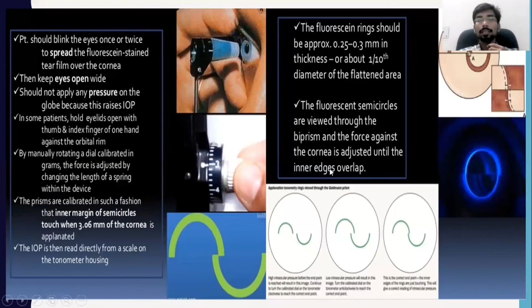Fluorescein rings should be approximately 0.25 to 0.3 mm in thickness, or about 1/10 of the diameter of the flattened cornea. Fluorescent semicircles are viewed through the biprism, and the force against the cornea is adjusted until the inner edges of the prisms are overlapped.